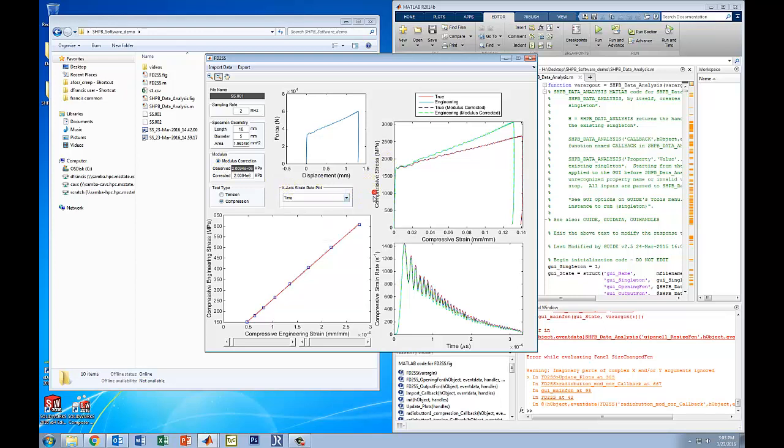Finally, there is a plot down in the bottom right to show the strain rate. You have the option of changing the x-axis there from time to strain, to true strain or engineering strain. Any of this data, your stress strain, your strain rate, true strain data, can all be exported. Everything can be exported, or you can pick particular curves and export them.